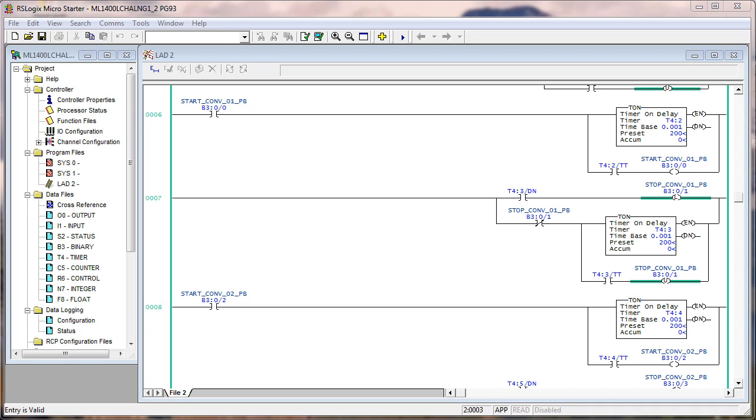Why do the conveyors toggle on or not? In other words, why are they doing what they're doing? And I would just say no system enable. When you toggle the system stop push button in step F, did everything stop? Yes. And the why is it dropped out the seal-in logic. You might have a more wordy explanation if you like, as long as it means the same thing. How many push buttons are you simulating in this exercise? I'm saying 8, 2 for system enable and 2 for each of the conveyors.